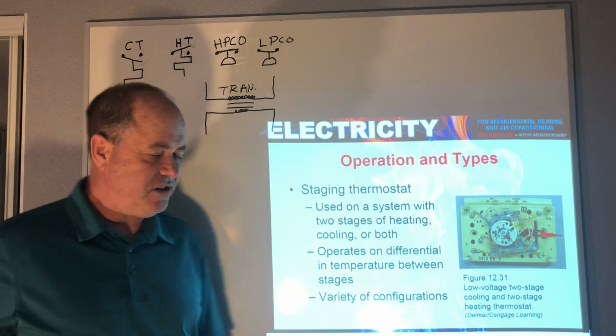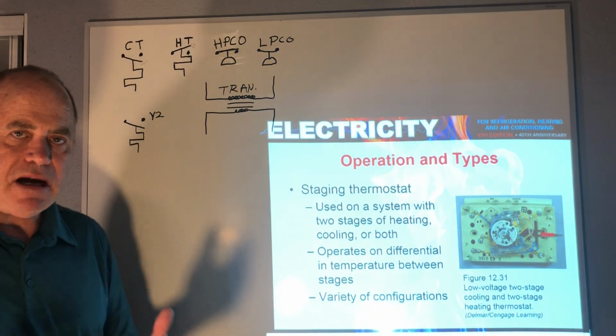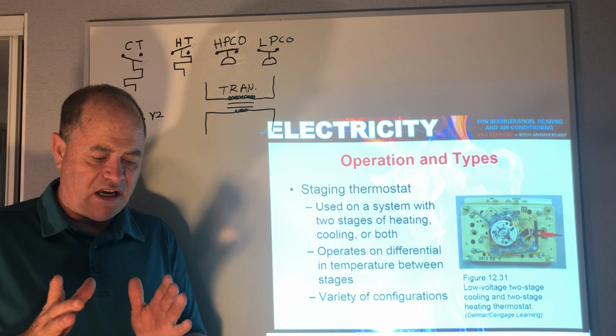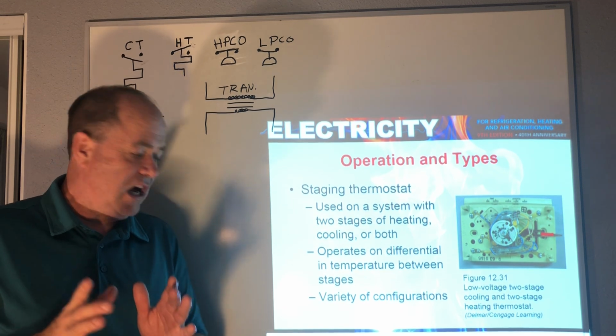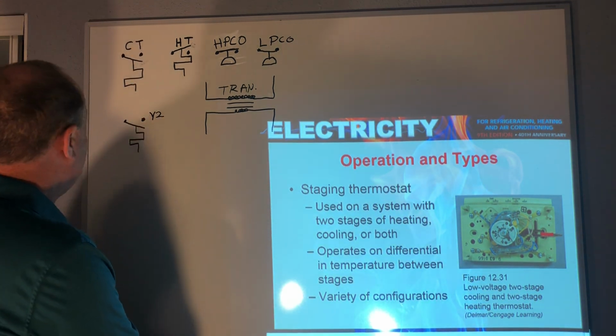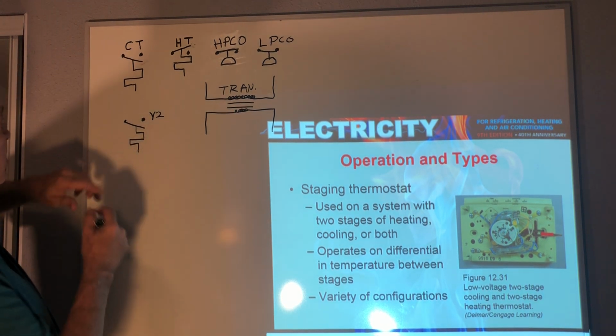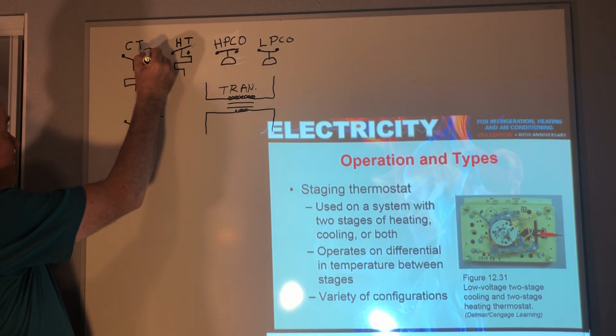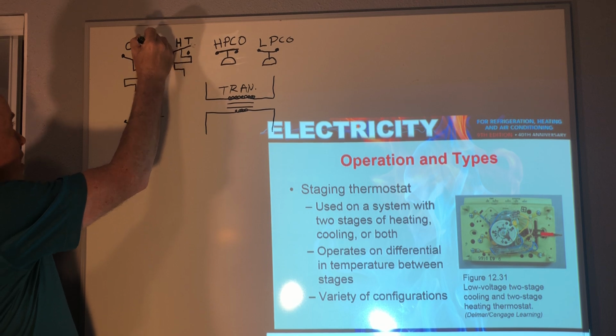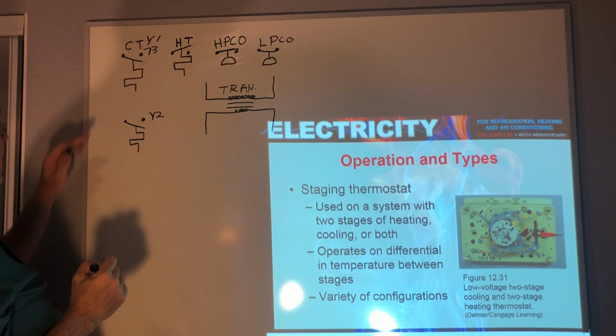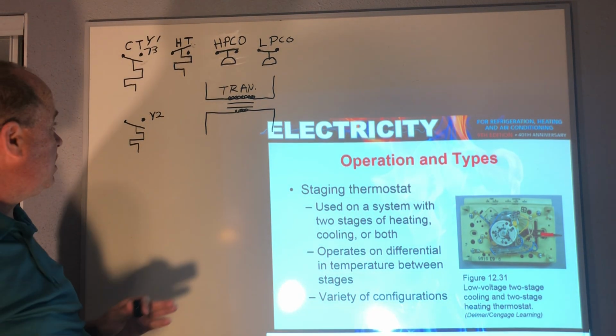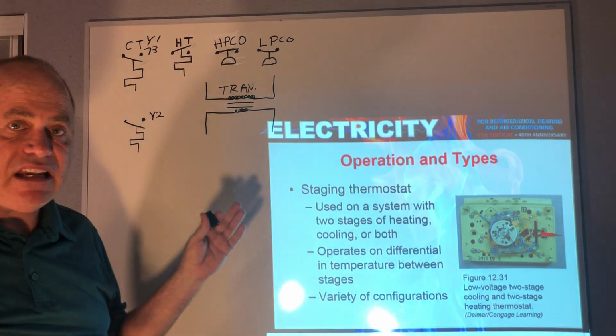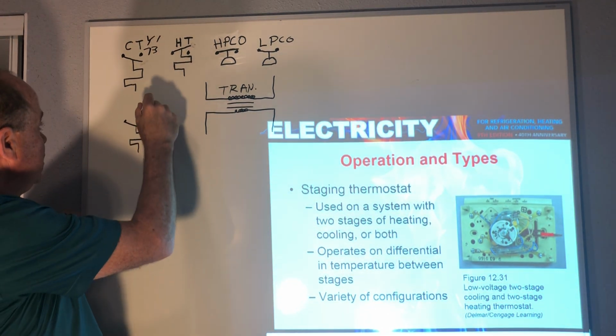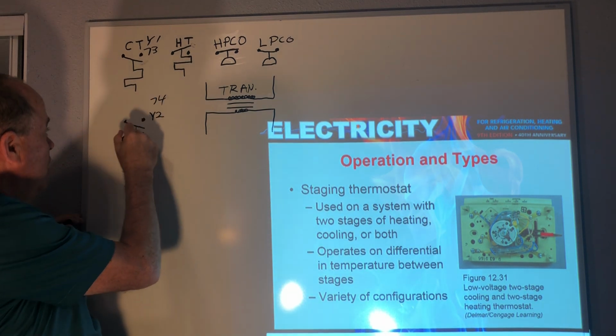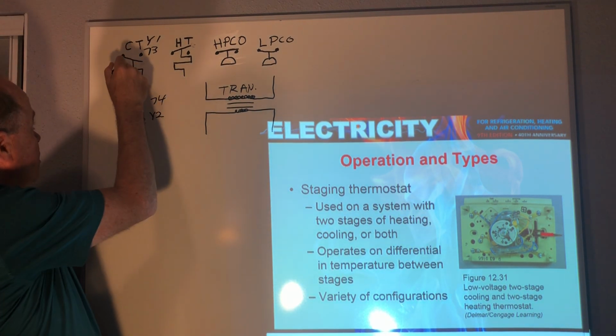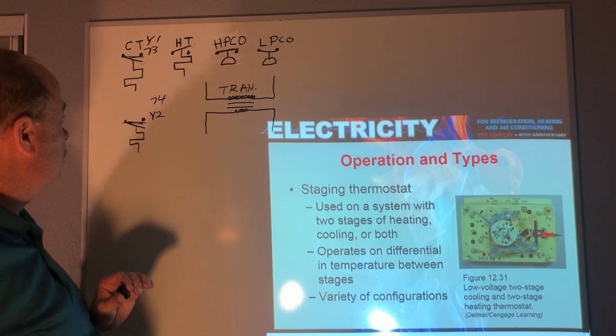Now, on staging thermostats, a lot of times we talked about how the terminal on the thermostat is Y. So here we have a cooling thermostat. Let's say the temperature rises up to 73 and comes on, which is Y1. And then if the temperature were to keep rising because that wasn't handling it, and it got to, let's say, 74, then this would close and Y2 would come on, and you bring on full cooling.